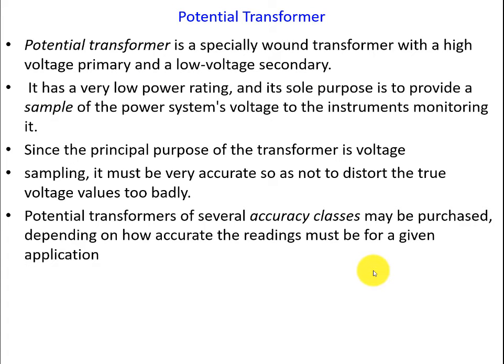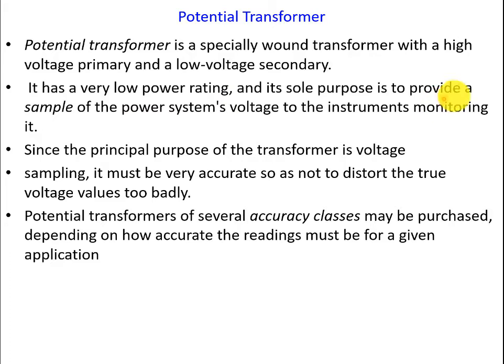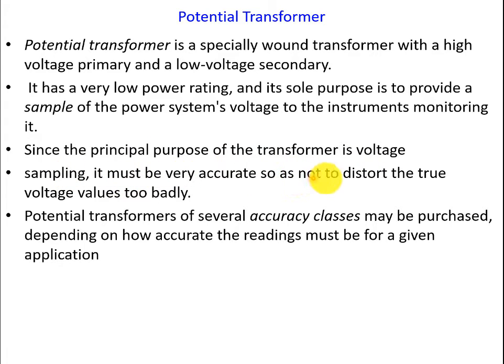The potential transformer is a transformer with a high voltage primary and low voltage secondary. It has a very low power rating and its sole purpose is to provide a sample of a power system's voltage to the instrument monitoring it. Since the principal purpose of the transformer is voltage sampling, it must be very accurate so as not to distort the true voltage values too badly.